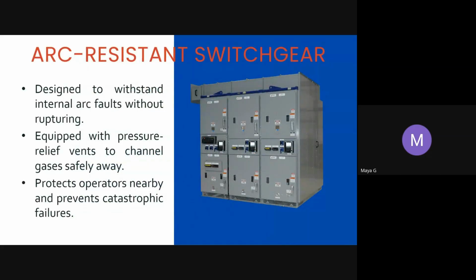Arc resistant switchgear. Our equipment should be designed in such a way that it can withstand internal arc faults without rupturing. This is one such switchgear, and it is equipped with pressure relief vents to channel gases safely away. This will protect the operator standing near the switchgear and prevents catastrophic failures.